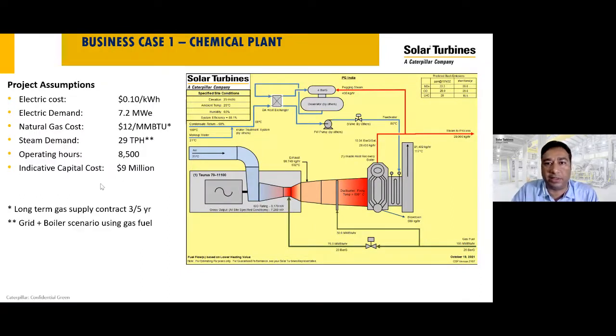The first case is of a chemical plant, a typical gas turbine plus HRSG kind of solution, where the utility requirements are 7.2 megawatt of power and 29 TPH of steam. The electricity cost is considered as 10 cents, and natural gas cost with a long-term gas supply contract is around $12 per MMBTU. The plant is a continuously operating plant, 8,500 hours per year.